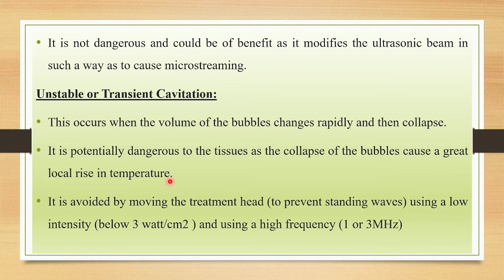That is mainly because of the formation of these unstable or transient cavitations. And that is the reason why we always treat in a circular or figure of eight pattern. So we move the ultrasound head in a systematic manner, in order to avoid these burns as well as unstable cavitation, which is one of the dangers of ultrasound treatment. Next effect is the microstreaming effect.